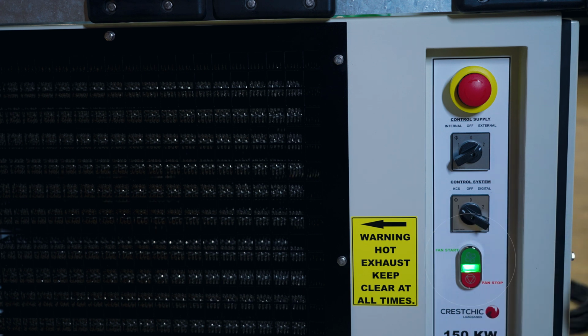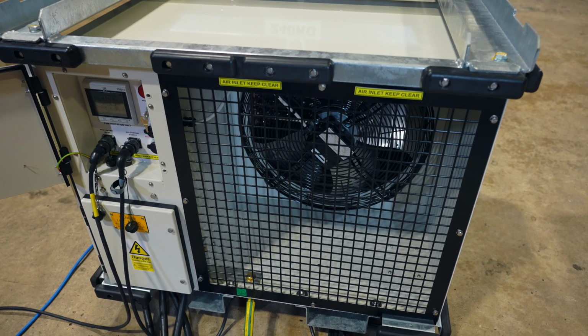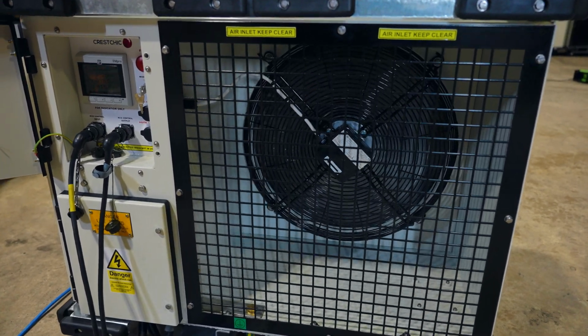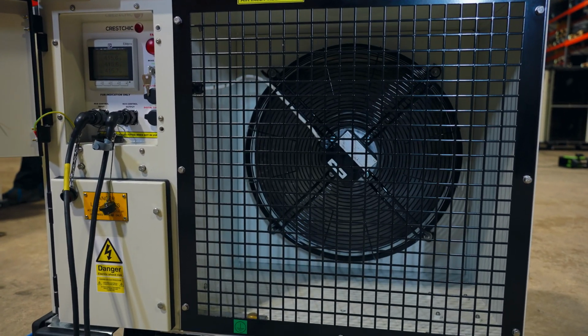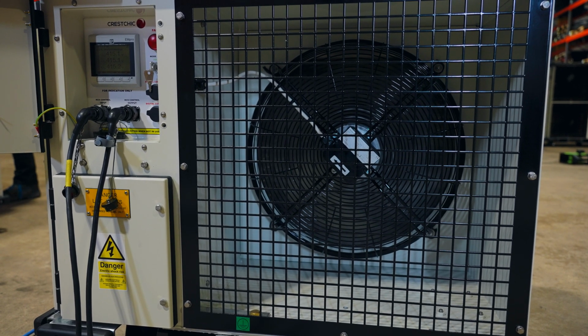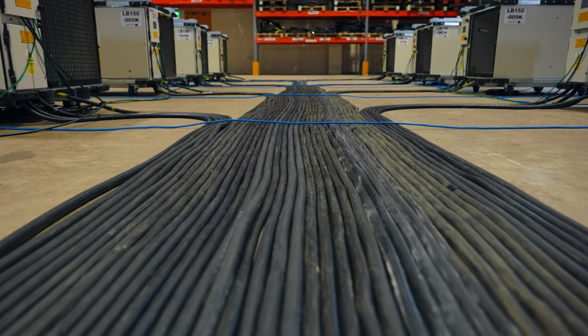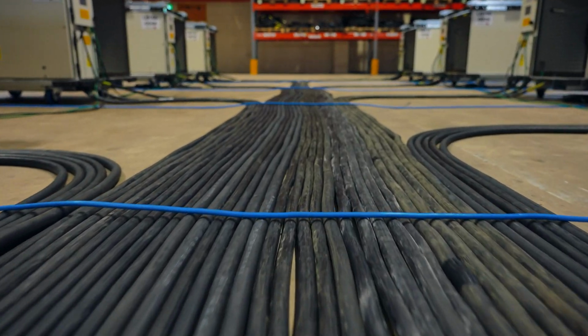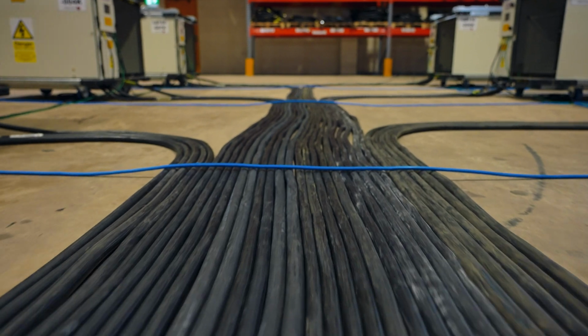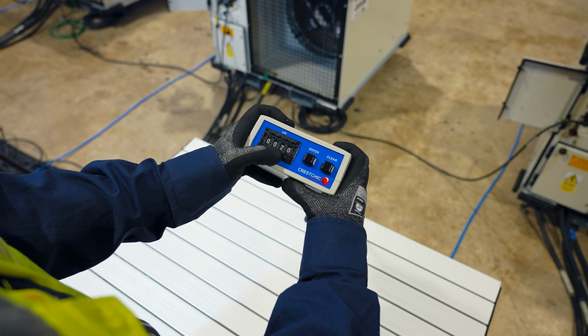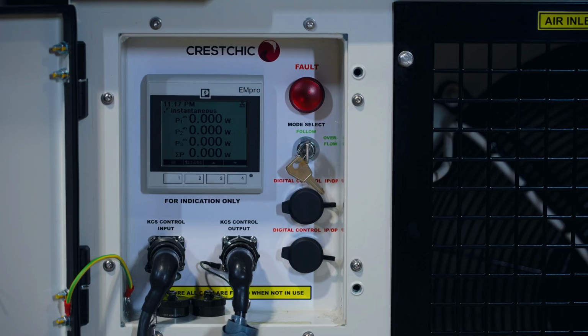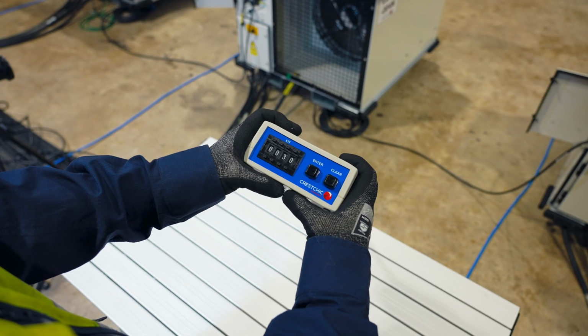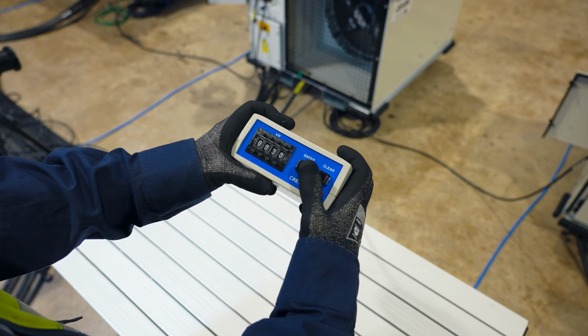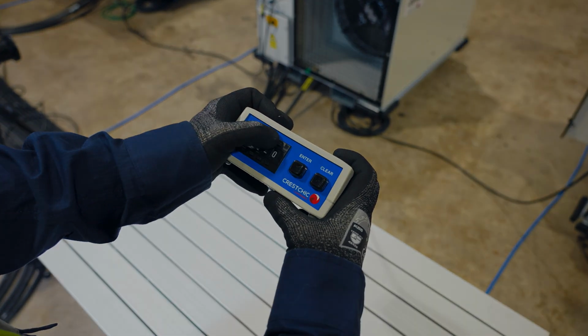We can now press the start button on each of the load banks, where the cooling fans will start. At this stage, the load supply can be switched on to the load banks, and once this is present, it is possible to see the voltage on the load bank's instrumentation meter. We are now ready to apply load. We have the load bank set in follow mode. Therefore, with the 8 load banks we have connected together, we are going to apply 30 kilowatts on the controller, which will apply 30 kilowatts onto each load bank, resulting in 240 kilowatts total load. This can then be observed via the load bank's instrumentation. Other loads can be entered and applied. When removing load, simply press the clear button and will remove all applied load.